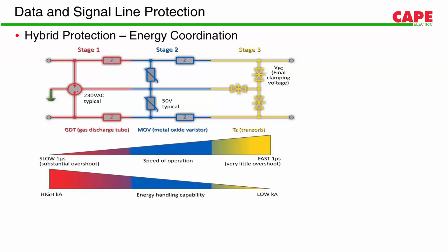So we provide another component, an impedance. It can be a resistor or inductor placed between stage 2 and stage 3 in such a way that there is a voltage drop across this impedance that ensures the MOV operates. In this case, a 600 volt diode was used and the MOV was 800 volt, so we ensure an impedance of such a rating that it makes a voltage drop of 200 volt across it, so that in stage 2 the MOV also operates. Similarly, between stage 1 and stage 2 we put a component which ensures there is a voltage drop across it, which makes the GDT also operate.